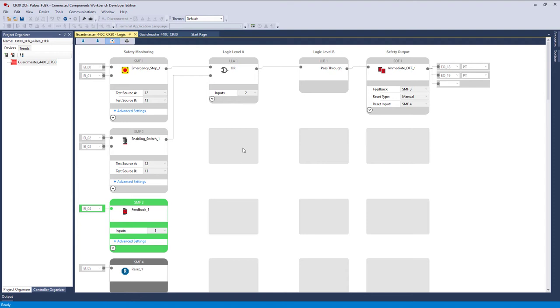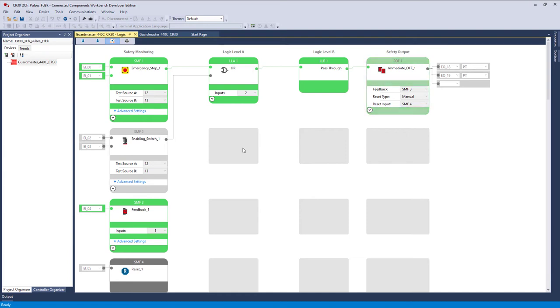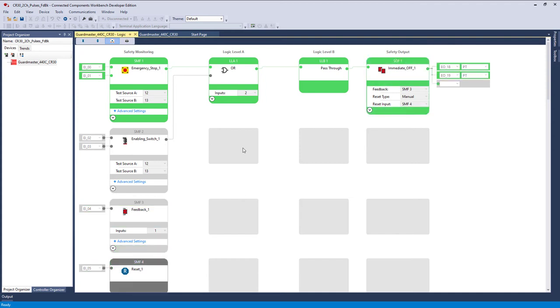Now I'm going to pull the e-stop back out. And you notice that the immediate off is not green. It's flashing green gray. That's because it needs reset. Remember the reset type now is manual. So I'm going to push the blue button. And now we're reset. How simple was that? Let's look at the hardware.